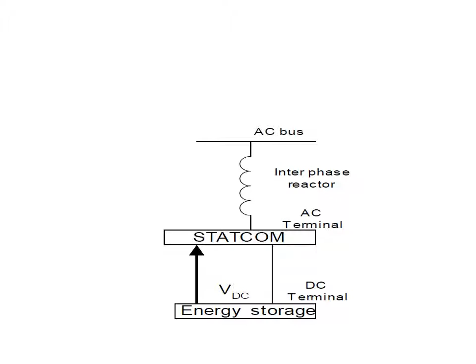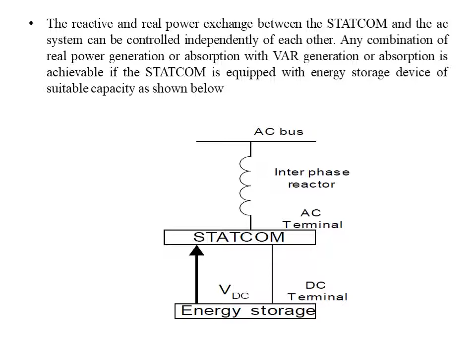The reactive and real power exchange between the STATCOM and the AC system can be controlled independently of each other. Any combination of real power generation or absorption with var generation or absorption is achievable if the STATCOM is equipped with an energy storage device of suitable capacity, as shown below.